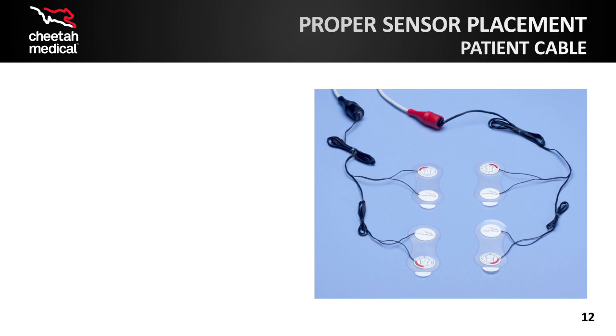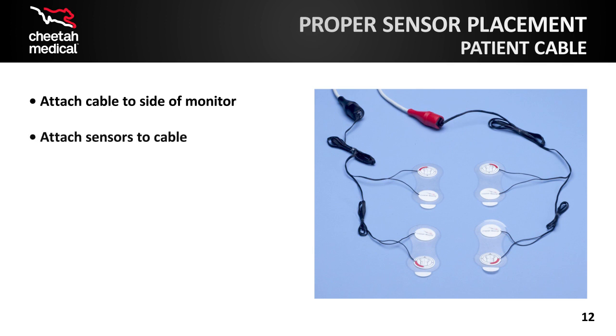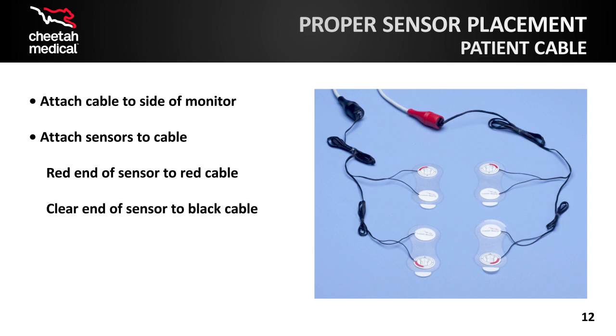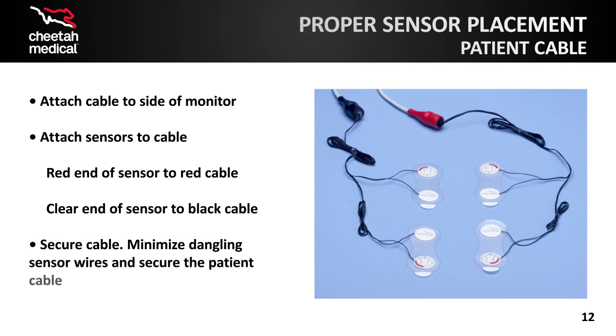The patient cable attaches the Cheetah monitor to the sensors which are applied to the patient. First, attach the patient cable to the back of the Cheetah Starling SV monitor. The patient cable location is clearly marked on the back of the monitor. Then attach the colored ends of the patient cable to the proper attachment on the sensors. The red attachment on the sensors goes into the red attachment on the patient cable. The clear attachment on the sensors goes into the black attachment on the patient cable. Once the attachments are secure, please secure the cable so that there is no dangling in the cable that may catch on other equipment or pose a tripping risk to other clinicians in the room.